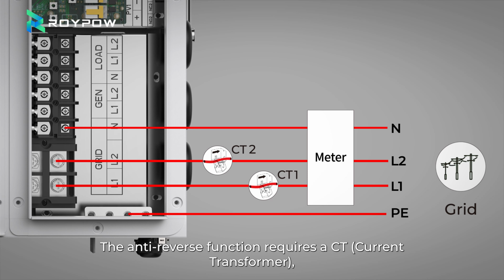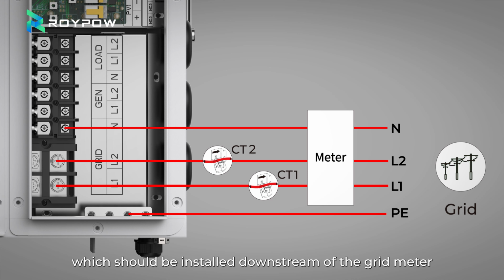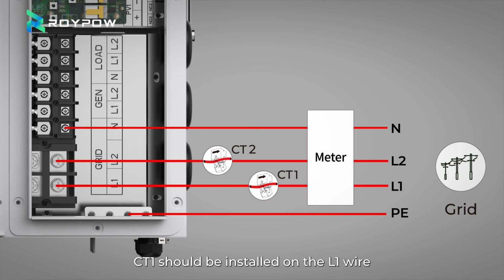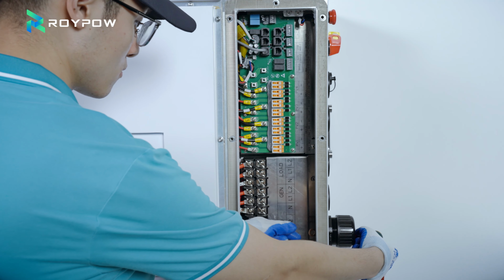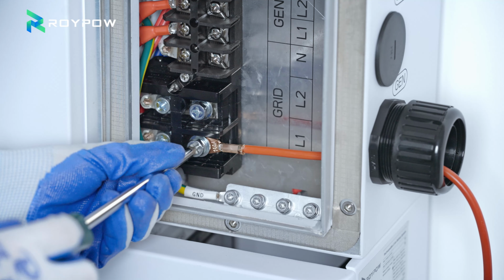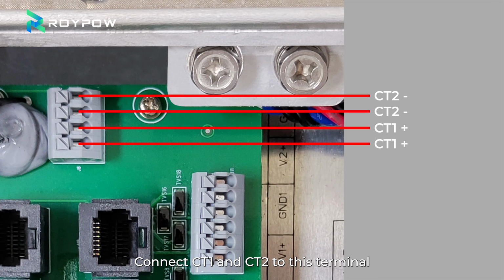The anti-reverse function requires a CT, current transformer, which should be installed downstream of the grid meter. CT1 should be installed on the L1 wire, and CT2 on the L2 wire, with the arrows on the CT pointing toward the grid. Connect CT1 and CT2 to this terminal.